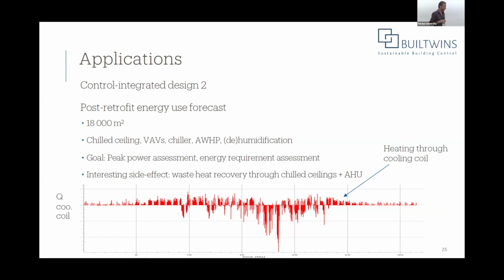What's happening is that MPC is disabling the heat recovery of the air handling unit. It's drawing heat from the chilled ceilings, passing that through the cooling coil, and preheating the air using that heat. By doing so, you don't need the chiller to run to cool the zones that need a little cooling, and instead you can use just a bit less heat recovery.